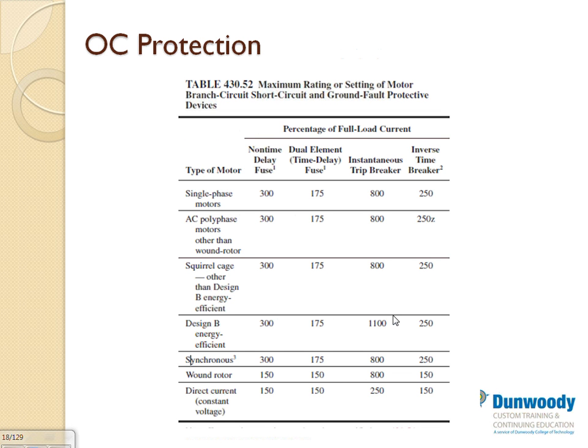Now, for motors, we have 2 protections: overload and short circuit. This table will get you to size short circuit. And I always like to use an example. Suppose that we have a 100 amp motor, and I use the amps because it's easier. I don't want to go to the tables. I need to size an overcurrent protection device for it. You have 4 choices here: non-time delay fuse, dual element time delay fuse, instantaneous trip circuit breaker, or inverse time circuit breakers.